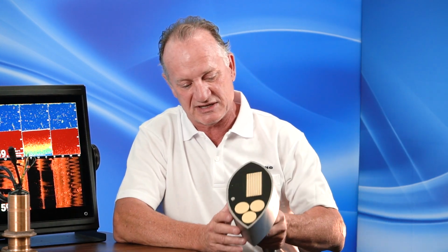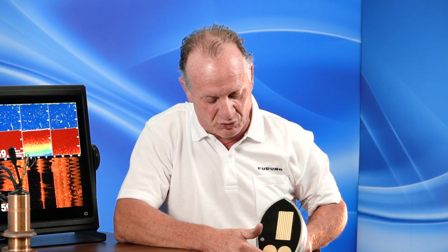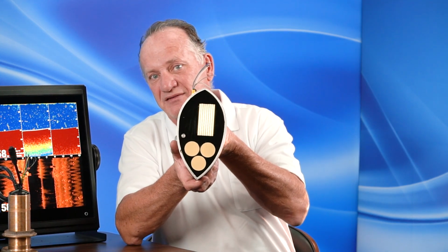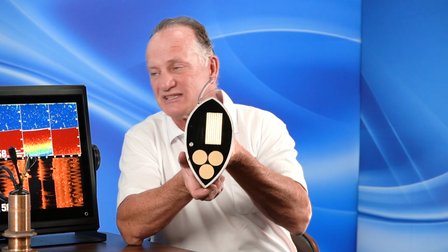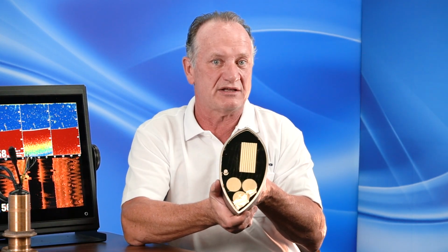So what we've done also, in addition to the single transducer DFF3D system, we've come up with some combo transducers as well. So if you don't want to put 3 or 4 holes in the bottom of your boat, you can just take a combo transducer. Here's an example of a combo transducer in a B260 housing that has individual 50/200 transmitter elements for the single beam system, as well as the DFF3D transmitter, as well as a temperature sensor. So you can see how we've stacked multiple functions into a single housing. And the receiving and the transmit elements are far enough apart, 50 and 200 versus 165 kilohertz for the DFF3D. So there's very little interference between the systems, and you can save a lot of time and money by combining those functions into a single transducer.